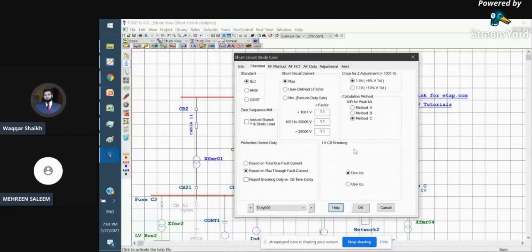If you don't select the options properly here, it will result in different values of peak currents, and these peak currents are used for bus bar electrodynamic withstand. Using the right method enables you to see the right short circuit levels, and those levels enable you to select the right bus with the right withstand capability.